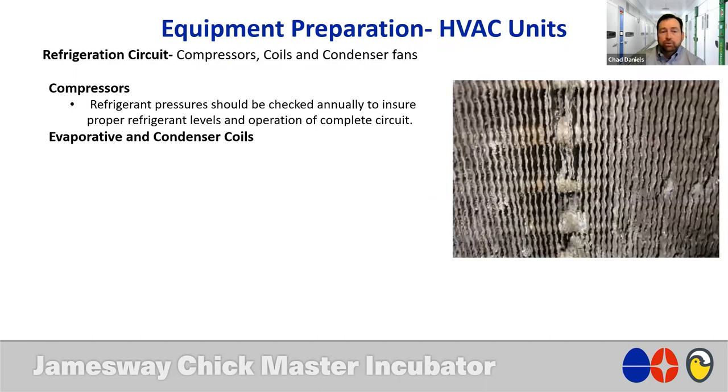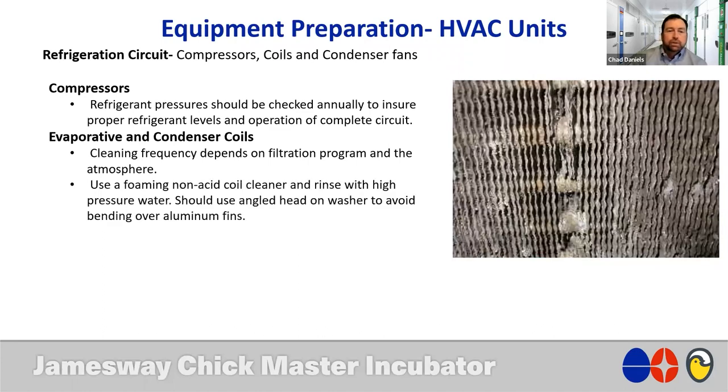When we look at evaporative coils and condenser coils, it's pretty obvious in this particular picture that I've shown here, the coil itself is pretty dirty. So we want to make sure that the coils are cleaned and are prepped and are going to be capable of absorbing the right amount of energy as the refrigerant circuit operates. Make sure you use a foaming non-acid coil cleaner.